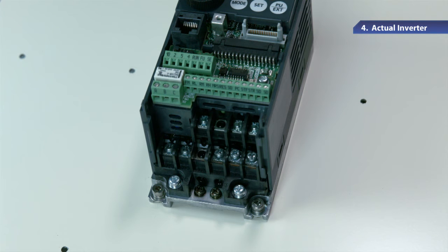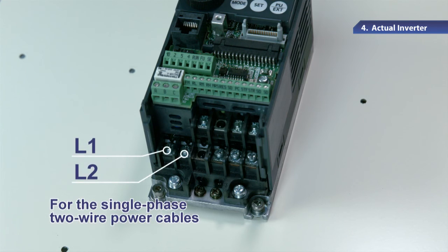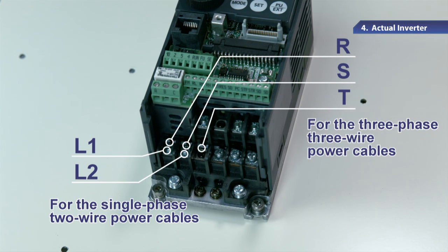First, please make sure the power is off. Then, connect the power cords to the inverter terminals. Connect the single-phase, two-wire power cables to the main circuit terminals L1 and L2. Connect the three-phase, three-wire power cables to the main circuit terminals R, S, and T.